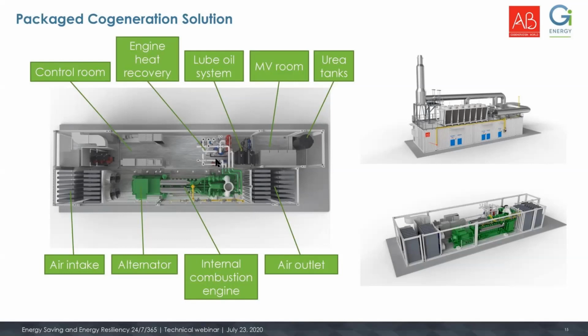The second source of heat, on the right side of your screen, is the exhaust gases. Once we leave the container, we treat the exhaust gases for emissions - we can discuss emissions in detail later, but these are low emission, lean burn engines that always include exhaust gas treatment in our supply for a plant in California. We treat the exhaust gases, then go into an exhaust gas heat exchanger that can produce hot water, steam, or further hot water to produce chilled water if needed in a production process.